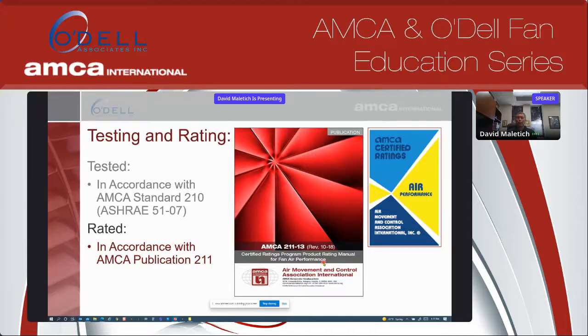So when we have an AMCA certified product that we manufacture or design, we'll build the product, design it, test it, and then we'll send the catalog data that we just created, along with our fan, to AMCA, which is a third-party validation organization. They retest our fan, and they have to be able to duplicate our catalog performance, plus or minus 2.5 to 3% on flow and pressure, and 5% on energy consumption, in order for it to be an AMCA certified product. If they can't do it, we cannot put this label on the fan and it will not be AMCA certified, unless we resubmit new data to them or we decide to use AMCA's data itself as a third-party validation organization.